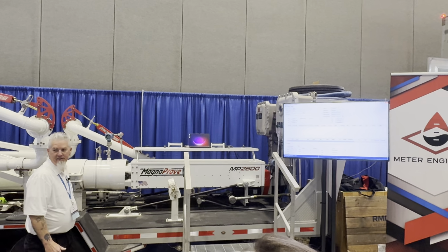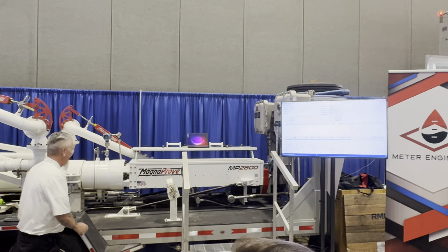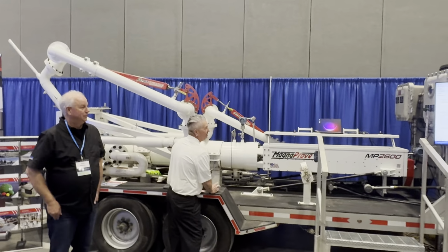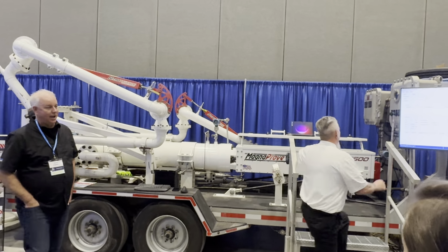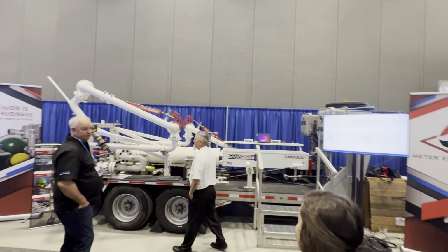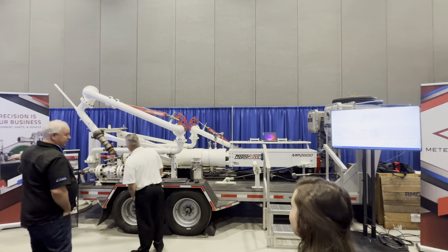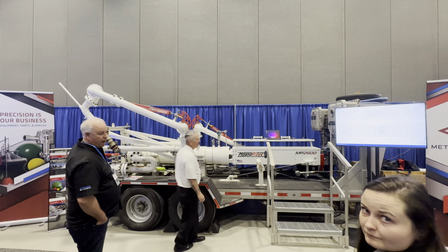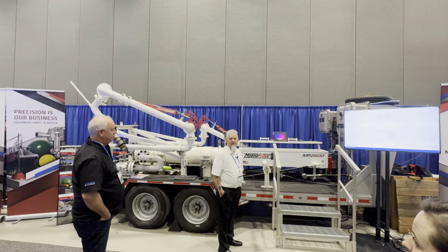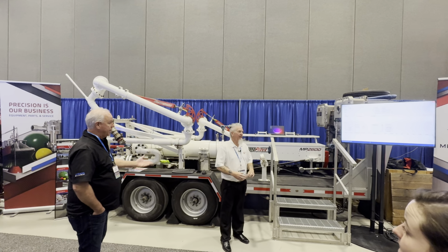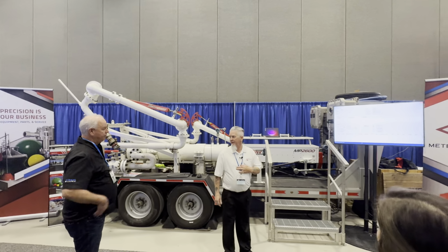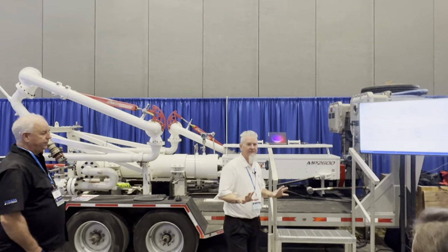Okay, now we're actually going to prove a meter right here for you guys. We've got a 2-inch Micro Motion meter behind the curtain over here. Maybe you can see it, it's right over there. We've got water, and we've got a pump that runs through this prover, through the meter, and back into the water source. We're actually going to prove this meter. What do you have it set at? It's set at running that same proof. How many passes? 5 out of 5 is what I've got it set at.